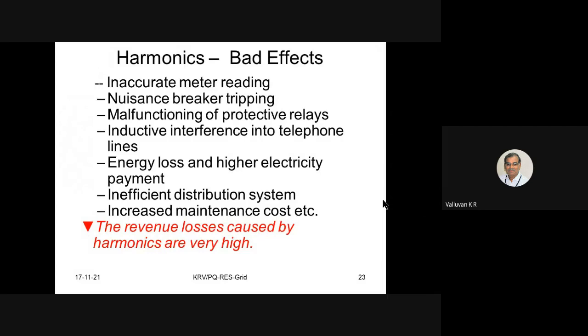Inaccurate meter reading: the electricity meter readings are inaccurate. Either they show more or they show less. Both are dangerous. Nuisance breaker tripping: breakers trip without any reason. Malfunctioning of protective relays. Inductive interference into telephone lines. This is one dangerous issue. Of course, today we don't have as much problem as we had 50 years ago, because we have more digital or even optical telephone circuits, but they cause interference, energy losses and higher electricity payment, an inefficient distribution system, and increased maintenance cost because equipment fails or loses its life. A transformer which is normally rated for 25 years, when there are harmonics in the system, can last only about 10 years. So in 10 years it fails. That is a big revenue loss for the system.